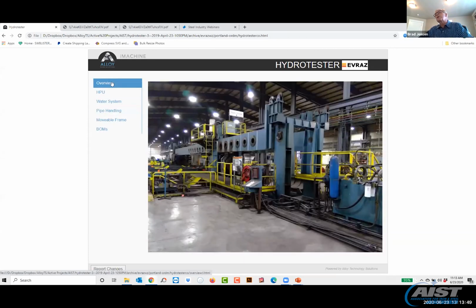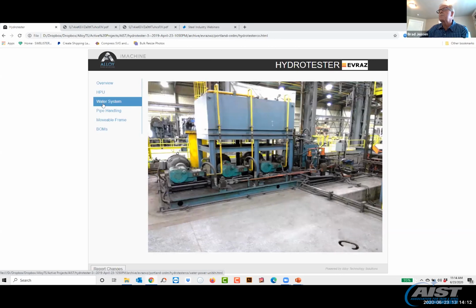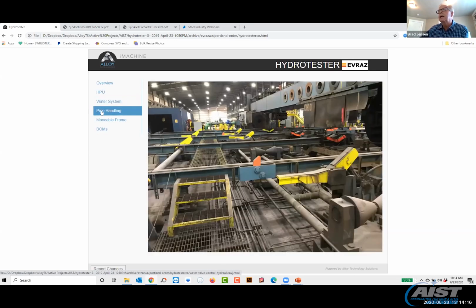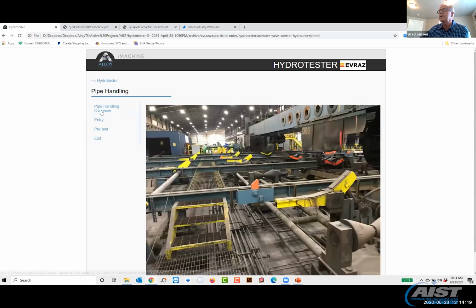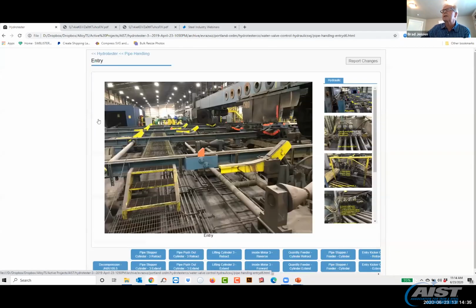So if I were looking at troubleshooting this on an outage, the first thing that's going to happen is that the operator or somebody is going to inform the troubleshooter that something is not happening or something is happening, and where is that occurring? Let me go, for an example, to pipe handling. Let's say that there's a problem on pipe handling, and within the category of pipe handling, we've got pipe entry, we've got pre-test, and we've got exit. If the problem is in entry, we simply click on entry.